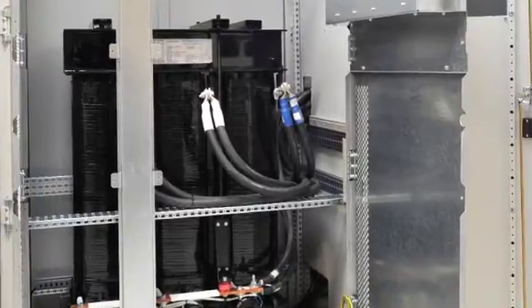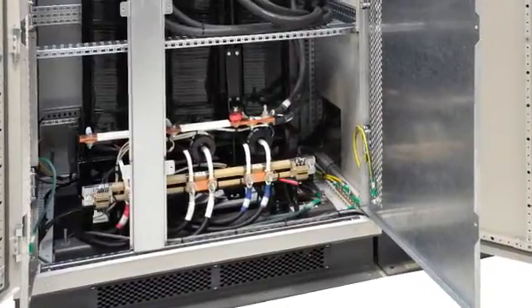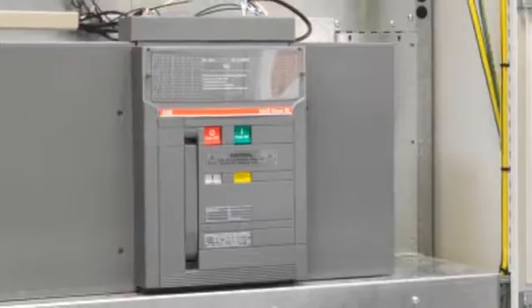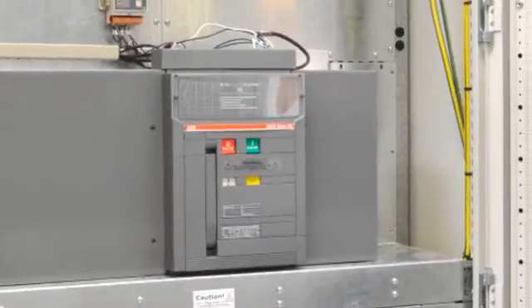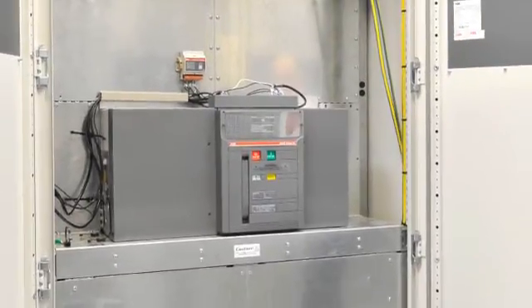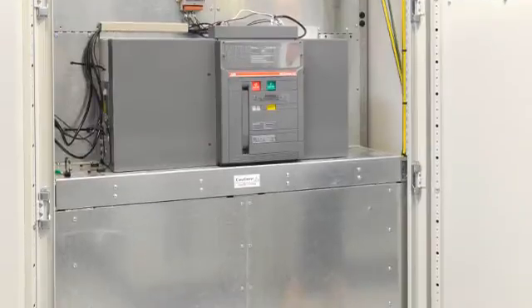The coupling transformer connects the inverters to the customer's load, provides a neutral, and adapts the inverters to the customer's system voltage. The fail-safe bypass, FSB, is an optional item that allows full automation of a wraparound breaker as well as providing backup protection to the load.